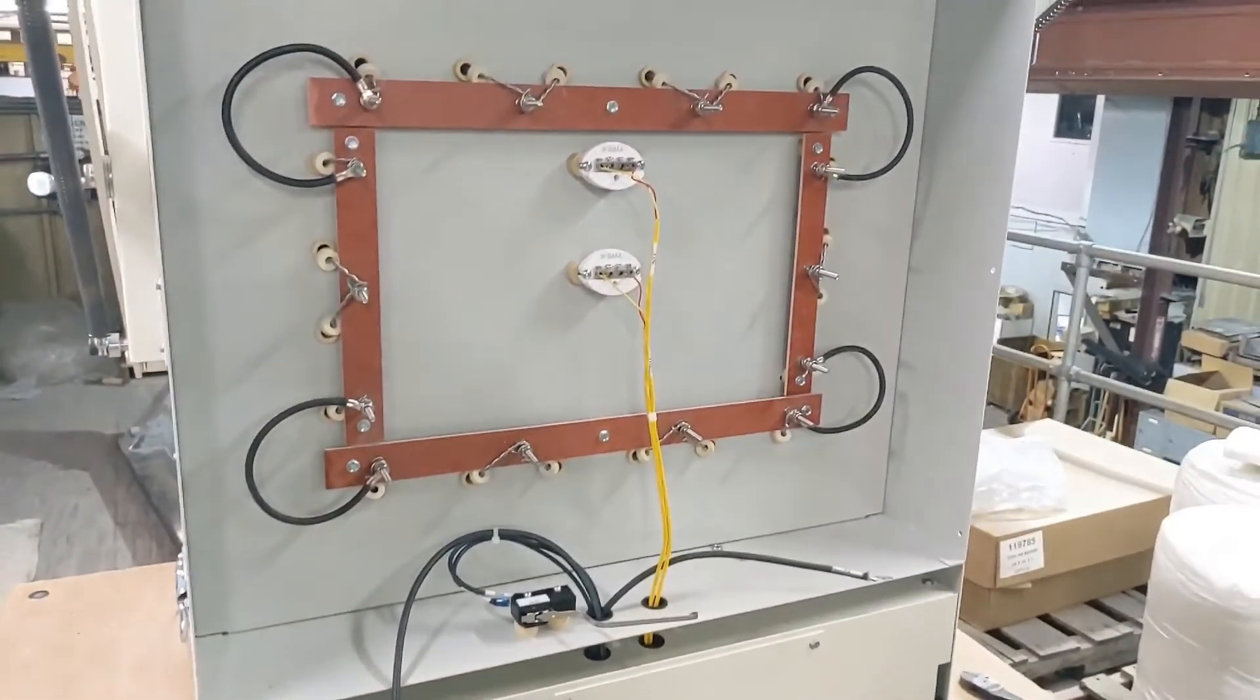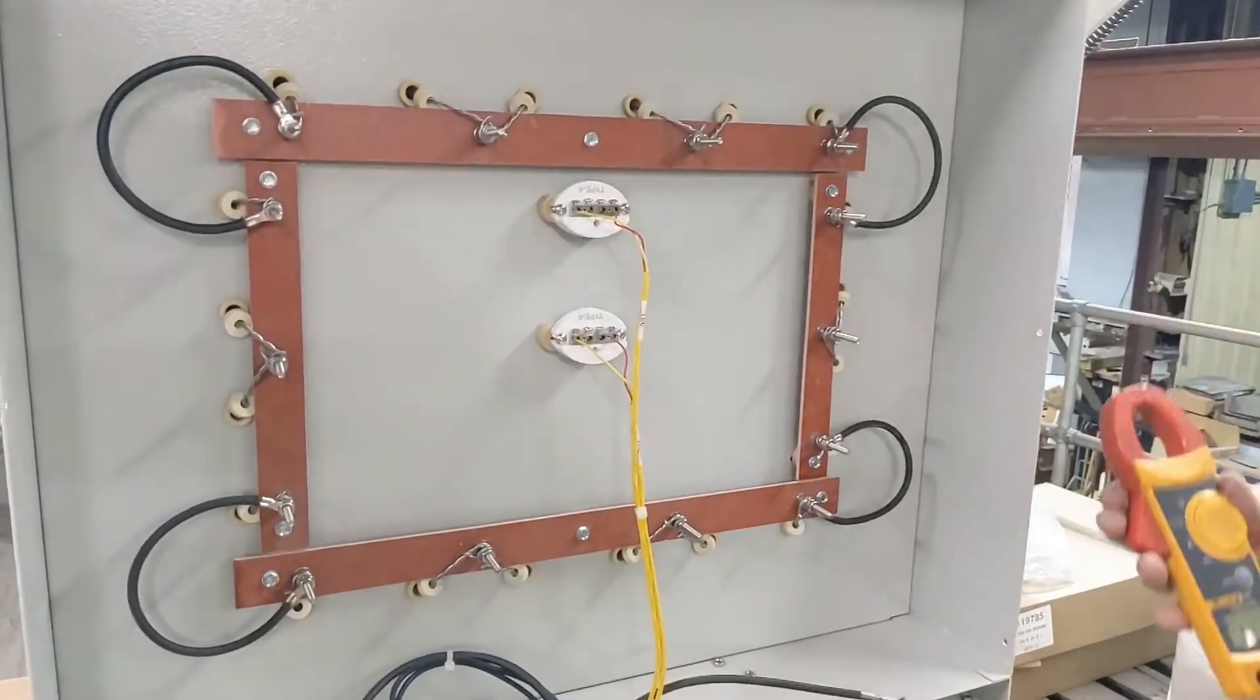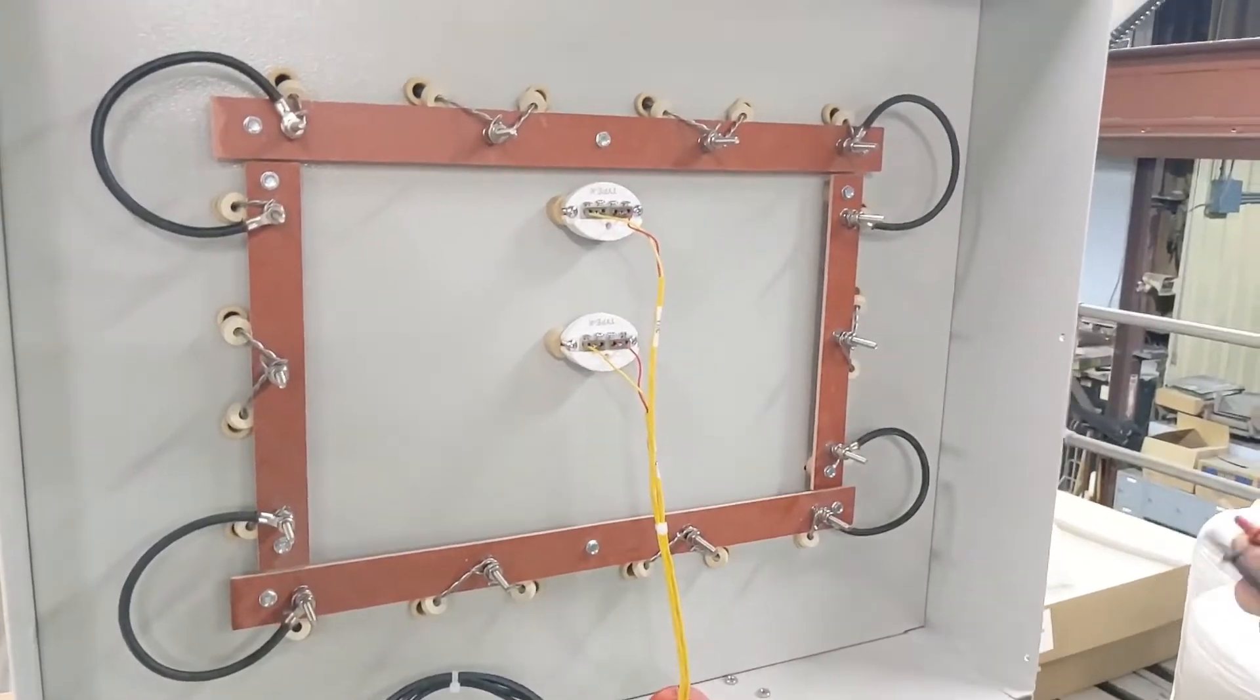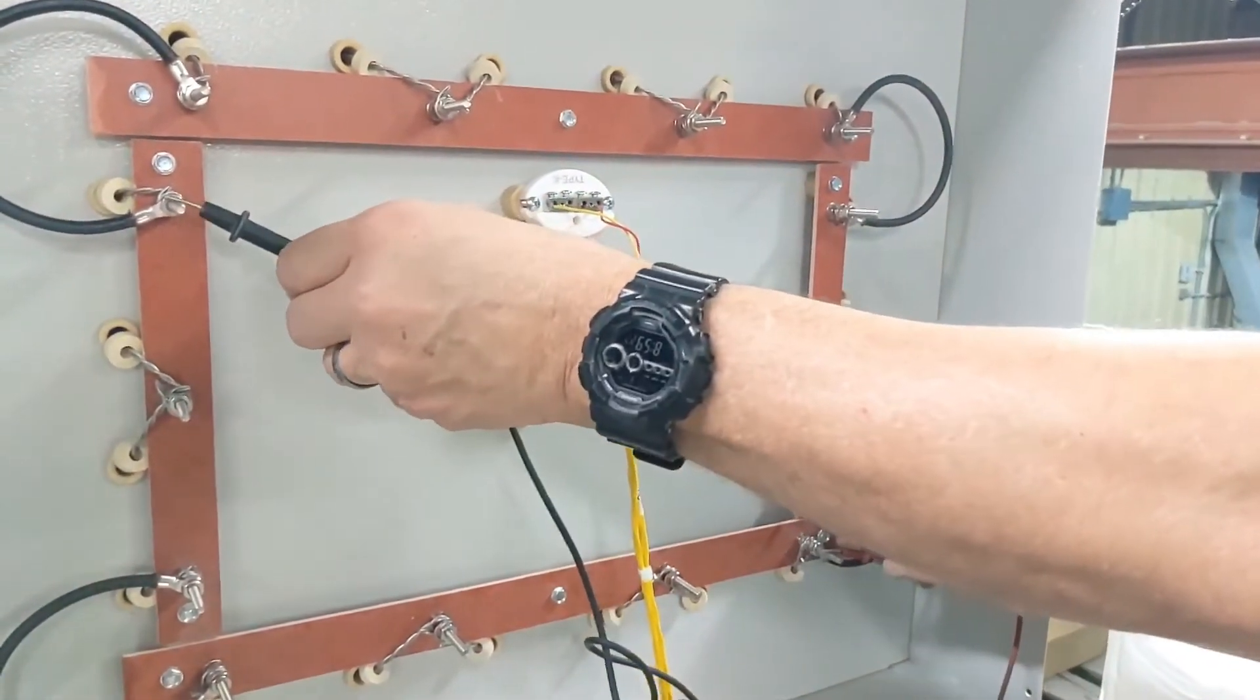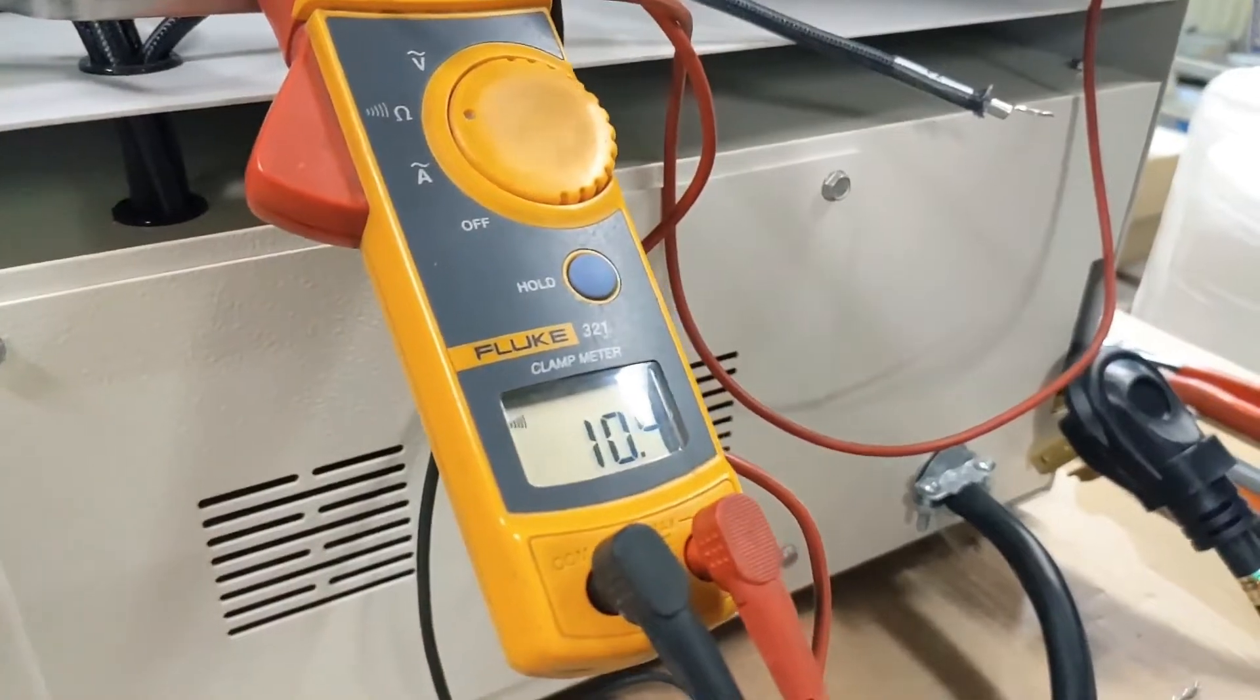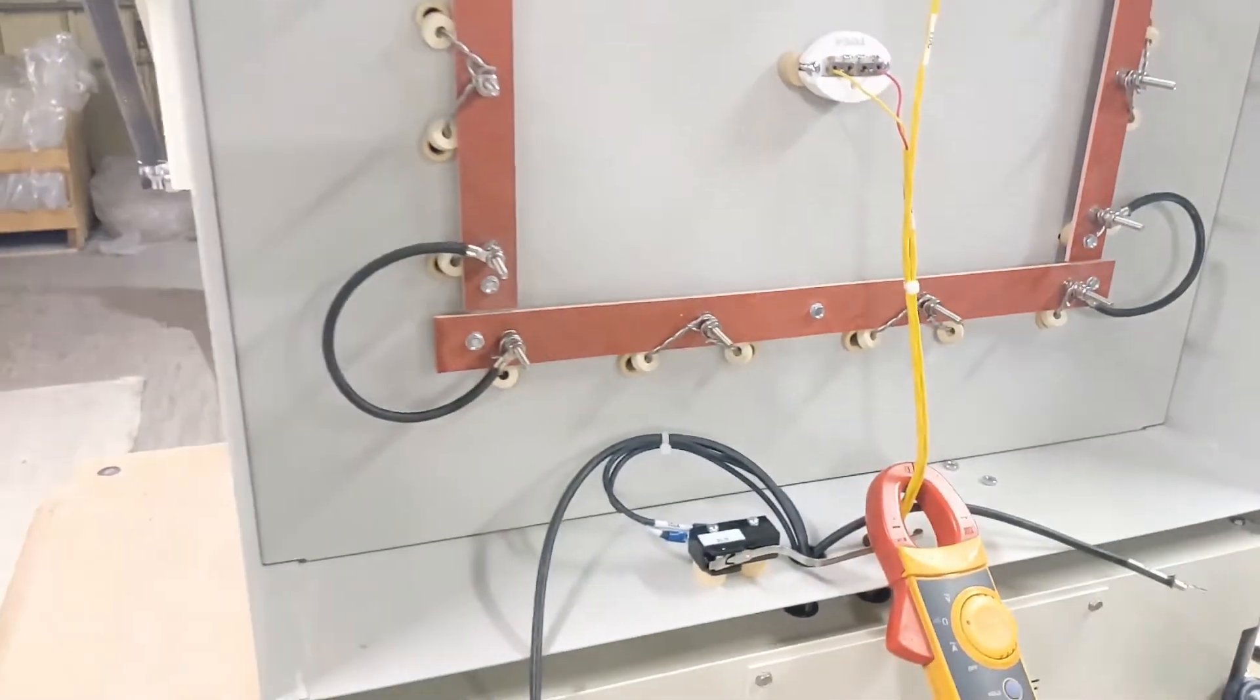Now the first step to checking that the elements are installed correctly is to check for resistance across the element loop. With a resistance meter, we want to check resistance on the studs shown. This will give us resistance through the full loop and we should be looking for about 10 ohms of resistance.